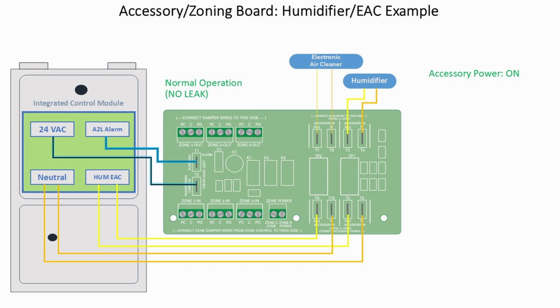control module. The T1 alarm A2L connection will run to the A2L alarm connection on the integrated control module. The accessory number 1 T9 hot terminal will run to the EAC terminal on the integrated control module. The T5 accessory number 2 hot terminal will run to the humidifier terminal on the integrated control module.